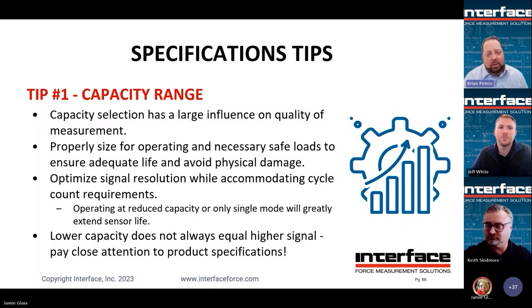The other thing to pay attention to is just because you may find another load cell somewhere else, or you may be looking at two, pay close attention to what the signal output is. It is commonplace for some people. We don't do it very often, only I think on a couple products where we'll offer a half calibrated load cell as a specific capacity. Most of the time we try to maintain the same output across all stated capacities. So again, you may be thinking you're finding a load cell that's rated for half the capacity, meaning you're going to have better signal or better measurement, but in reality, you're just getting half the output. So pay close attention to the outputs when you're comparing capacities.